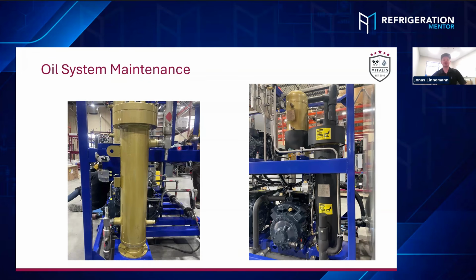Even if the pressure is gone, don't close the gauge manifold. Leave it open because the remaining oil will always bubble out some more CO2 pressure. And if you close the valve and then new pressure builds up, it takes you 5 minutes to loosen the top cap, then maybe you're back at 5 or 10 bar. And you don't want to open that top cap with 5 or 10 bar. So leave it open as long as it takes to open the top cap and make sure there's no pressure behind that. I love that.